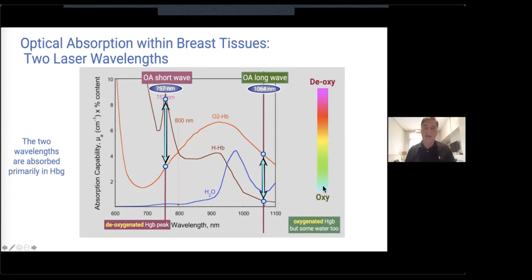The longer wavelength, 1064, was chosen not because it's the peak of hemoglobin, but because it's the widest separation between oxygenated and deoxygenated. And it also avoids a confounding water peak, because water and fat can also contribute to optoacoustics. And it's going to be demonstrated as green. So we have a color scale. The fuchsia and red end is the deoxygenated end, and the aqua and green end is the oxygenated end.